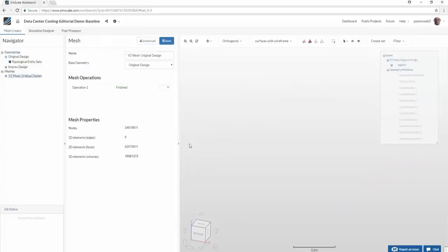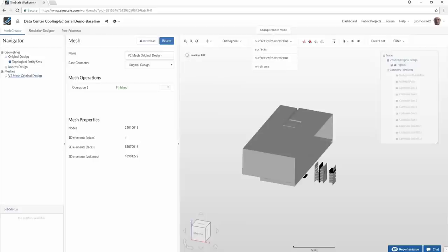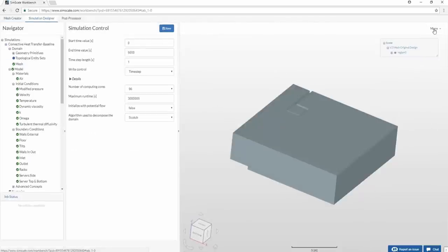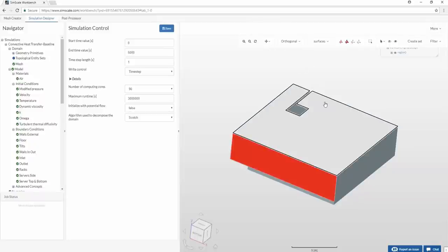In this case, we are dealing with a mesh that is over 18 million cells. We needed to have a sufficient mesh refinement in the areas that are connecting the underfloor compartment and the top part, and a sufficiently fine mesh around the servers themselves. This is also why it takes a second for the whole system to load.